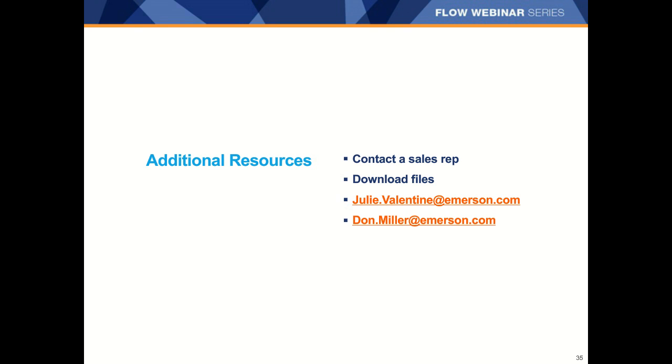Certainly. Some of the benefits of FSM include the ability to detect changes in corrosion rates much earlier than, say, ultrasonic thickness testing. It also allows for a broader area, since the sensing pins are all interconnected and do a comparative voltage comparison between them. And with the FieldWatch software, you actually get a 3D grid of what's going on, not just in a generalized way, but also possibly a localized corrosion or erosion event.